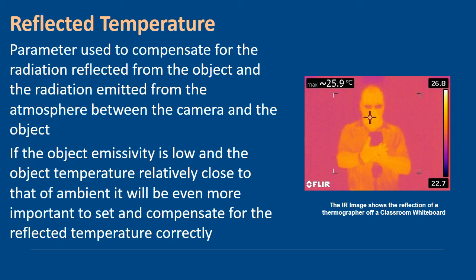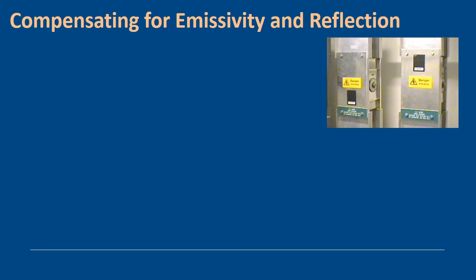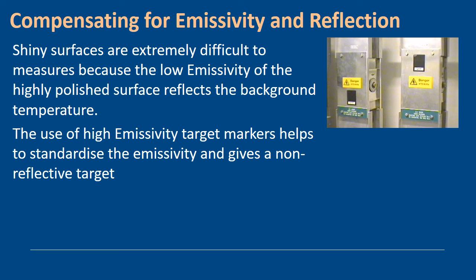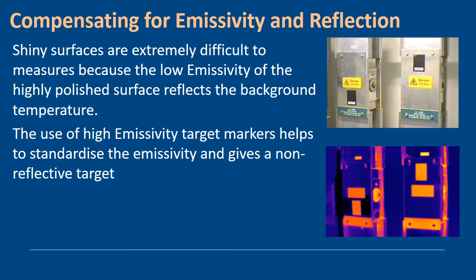So how do we compensate for emissivity and reflection? As I stated, shiny surfaces are extremely difficult to measure because of their low emissivities and the highly polished surfaces are affected significantly by background temperature. We use things like high emissivity target markers, the electrical tape I spoke about earlier, because they give us a non-reflective target with a known emissivity. Looking at this infrared image here, you can see that these tags are the IRISS label systems where we actually write joint temperatures, and you can see in the infrared image they're quite clear.